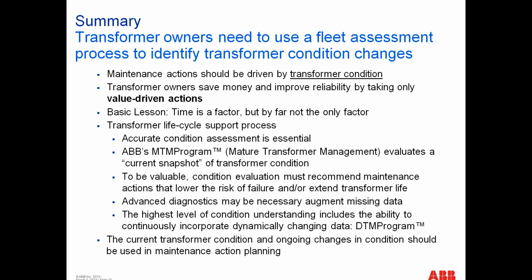What you want to do, to support your transformer and get the longest life out of it, is have an accurate condition assessment. As I mentioned, our condition assessment program has traditionally been a snapshot-based assessment, where we go to a customer's site, they provide us with data, we come home, and we determine the risk of failure of the transformer.